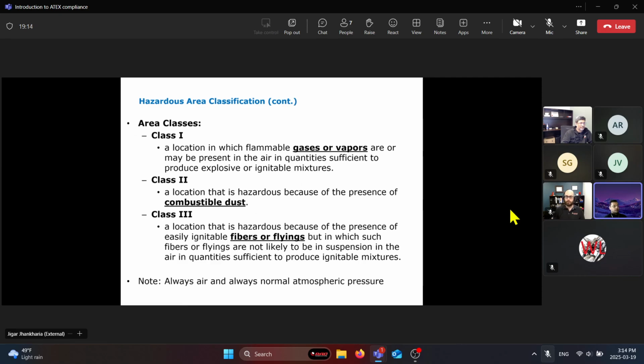Class 1 is a location in which flammable gases or vapors may be present in the air in quantities sufficient to produce explosive or ignitable mixtures. Class 2 is where combustible dust is present in the hazardous environment. And Class 3 is fibers or flyings. So when we say Class 1, we're only talking about gases and vapors. Your product is only certified to be used in an area which has gases or vapors, not combustible dust, fibers, or flyings.